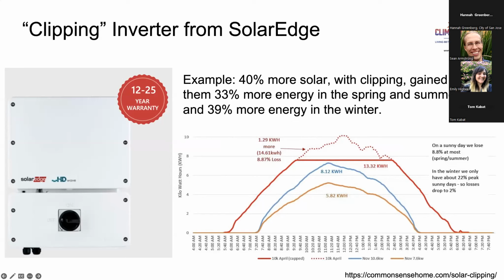So this inverter on the left-hand side allows you to plug in up to about 15 kilowatts when you can only technically put 3.8 kilowatts of AC into your panel. But you can connect 15 kilowatts with this inverter. That's pretty overkill, but hypothetically, that's what this does.